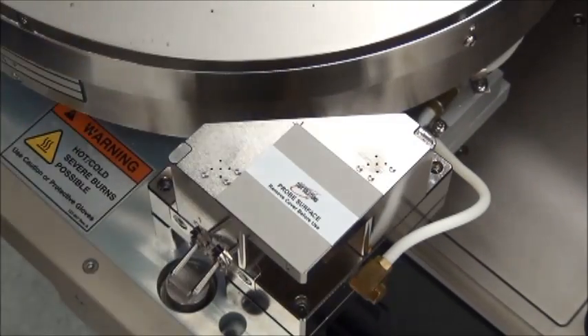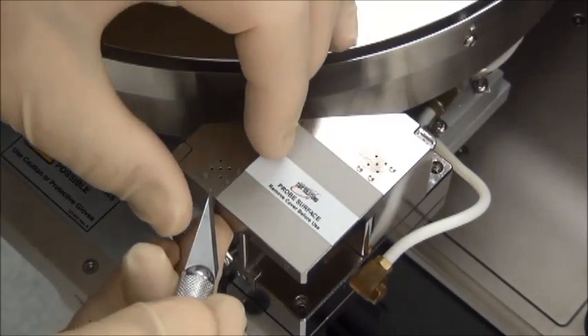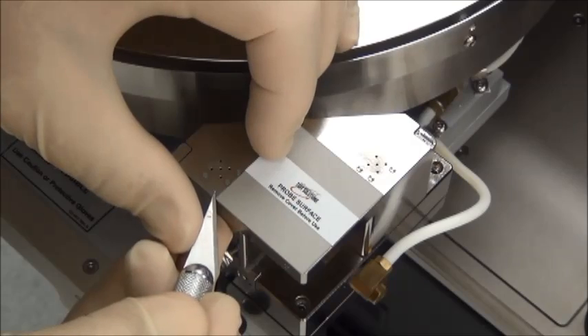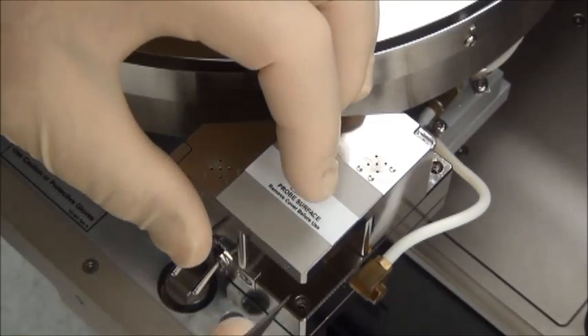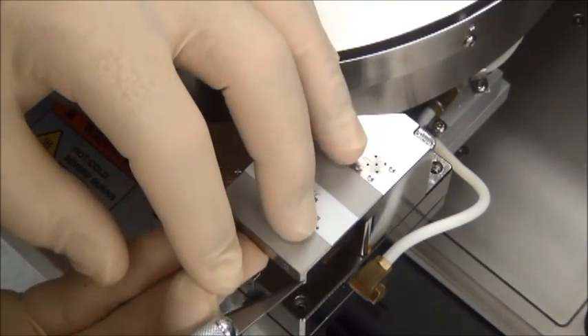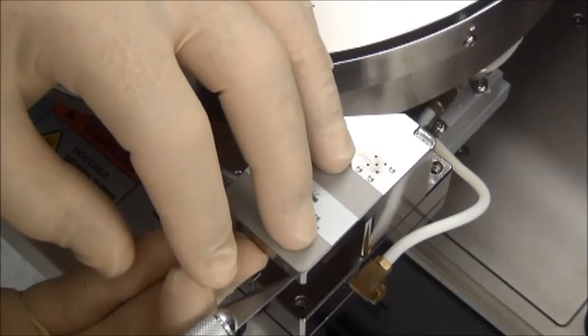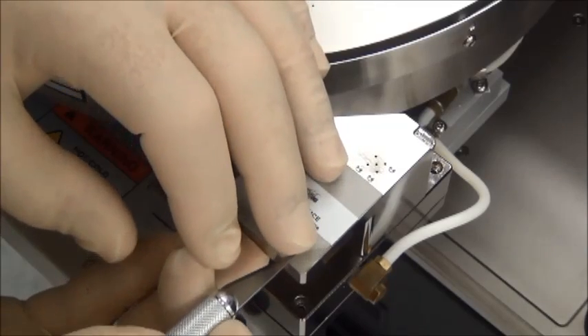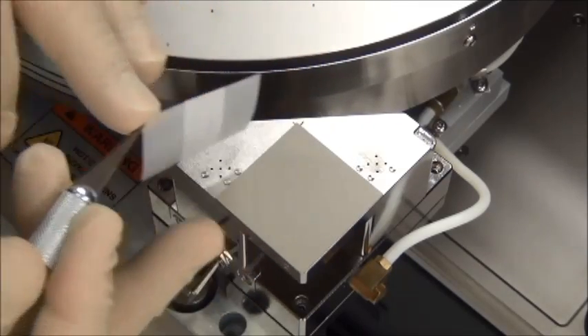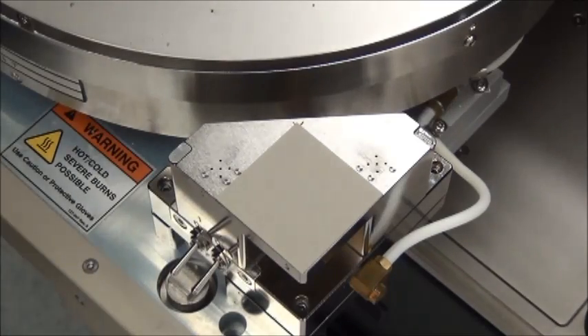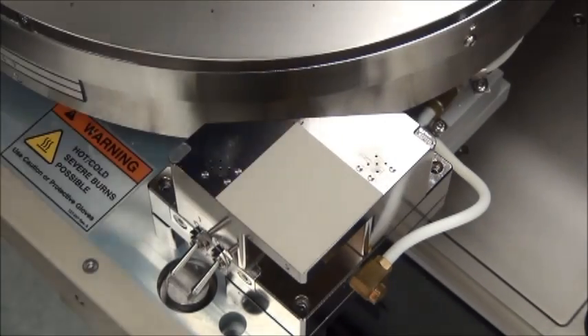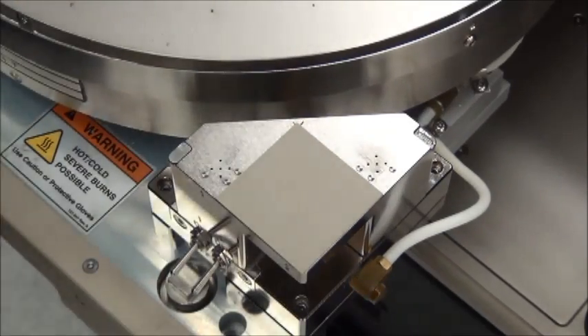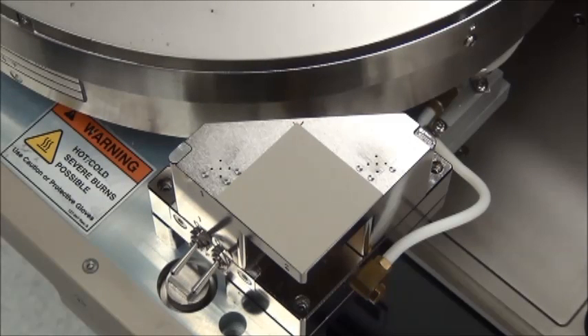Then lastly, once the pad is fully adhered to the chuck with no air bubbles, remove the protective cover from the top of the cleaning pad. Using a sharp edge, find a corner of the pad and carefully lift the cover off. And with the cover being removed, the installation of the cleaning pad is now complete.